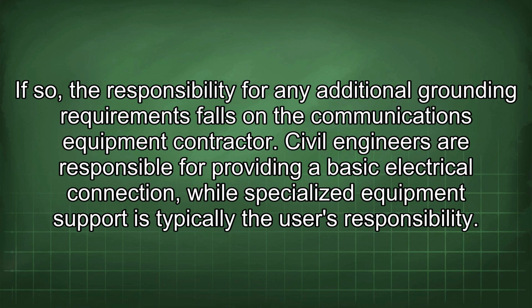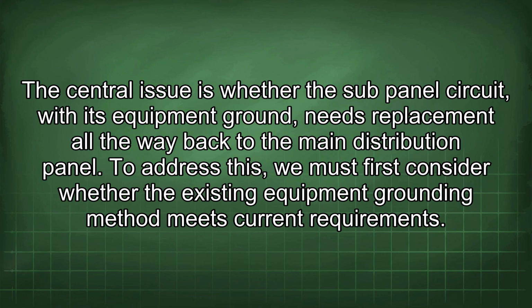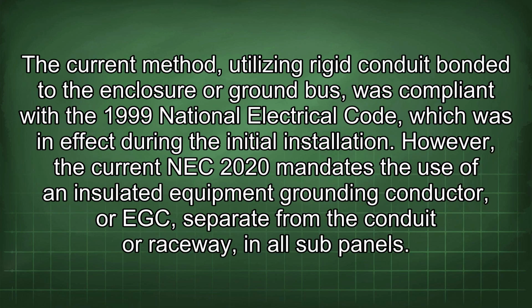Civil engineers are responsible for providing a basic electrical connection, while specialized equipment support is typically the user's responsibility. The central issue is whether the sub-panel circuit, with its equipment ground, needs replacement all the way back to the main distribution panel. To address this, we must first consider whether the existing equipment grounding method meets current requirements. The current method, utilizing rigid conduit bonded to the enclosure or ground bus, was compliant with the 1999 National Electrical Code, which was in effect during the initial installation.